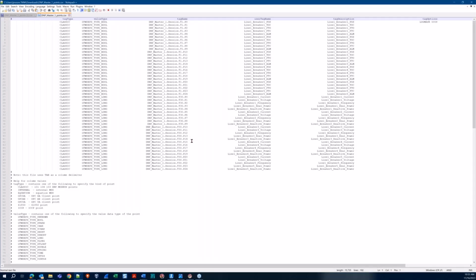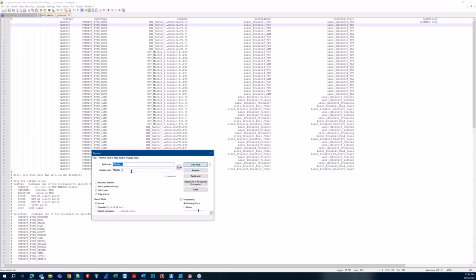And now we see a nice overview, really a CSV view of what's available inside of that points list. So we do see the user tag name. This is going to correspond with the alias name, the intelligent name that I gave the point, versus the tag name, which is really just the device, the session, the point type, T1, of course, corresponding to binary input in DNP, and then P0, the index. So to update this for my second DNP master, I'm just going to do a basic find and replace, master 1 with master 2. See, we've done 50 occurrences. That all sounds good because I have 50 points, 25 of each.